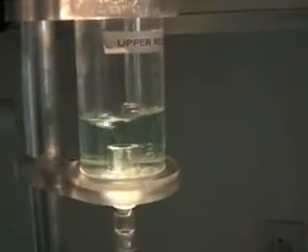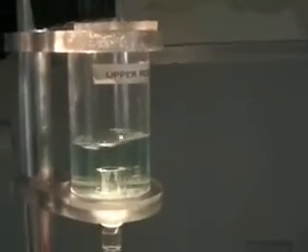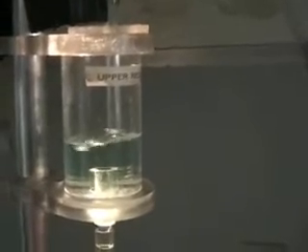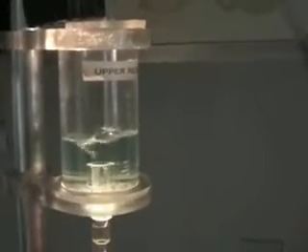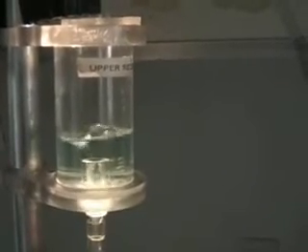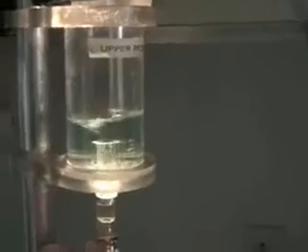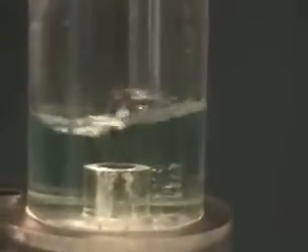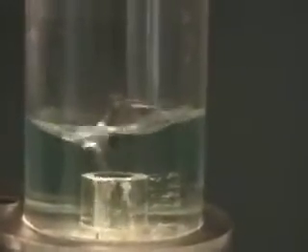So we'll run through one more cycle of this. I'm going to allow the level to go down and see how big a vortex we can get. There we go. We're starting to have a significant vortex. And of course the flow is going to drop even more because there's now more air entering into the pump, and we'll get more and more air and less flow.